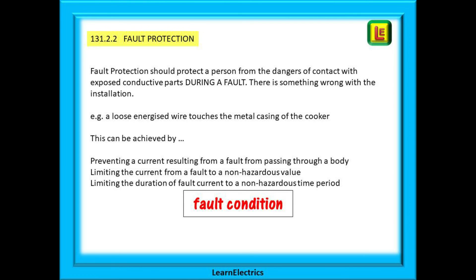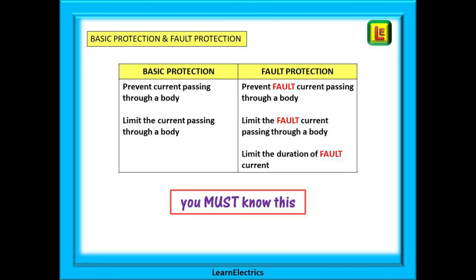Now look at regulation 131.2.2 — fault protection should protect a person from the dangers of contact with exposed conductive parts during a fault. It is telling us that something is wrong with the installation — for example, a loose energized wire touches the metal casing of a cooker. Protection can be achieved by preventing a current resulting from a fault from passing through a body, limiting the fault current to a non-hazardous value, or limiting the duration of fault current to a non-hazardous time period. This slide compares the two: basic protection is on the left, fault protection on the right. In the exam, a question on fault protection will require an answer using the word 'fault' — you must know the difference.